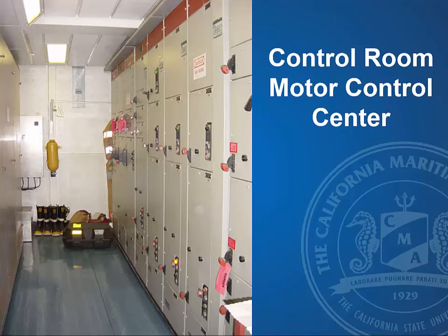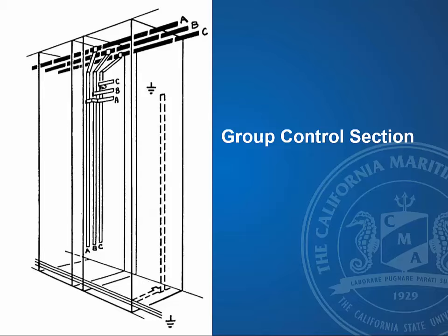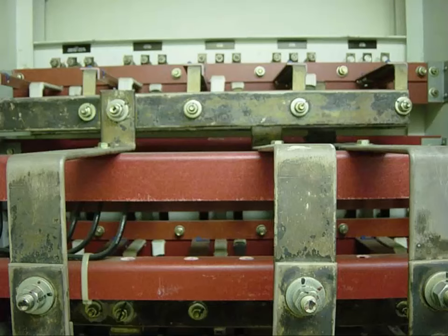All right, so you also have motor control centers, and these will have a large breaker off the main switchboard. And then there are bus bars behind these motor control centers, and they have various motor starters arranged on this. So this is how they're kind of segmenting out. Also, you notice that some are going to be vital equipment and some is non-vital equipment. And internal to them, they also have bus bars. And these bus bars will distribute the power to each of the individual circuit breakers. So this is actually what these bars look like in the back of one of these panels. This is actually off the emergency switchboard.